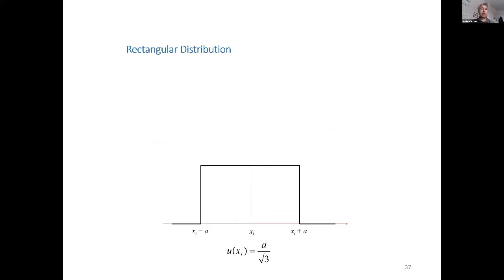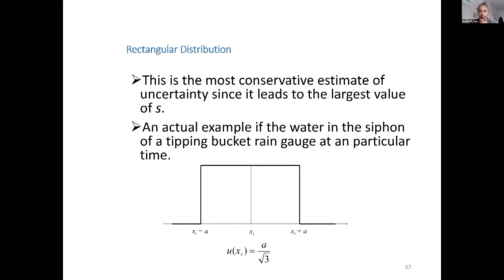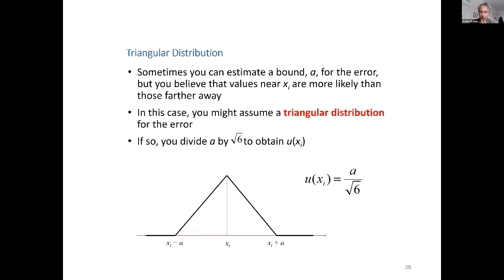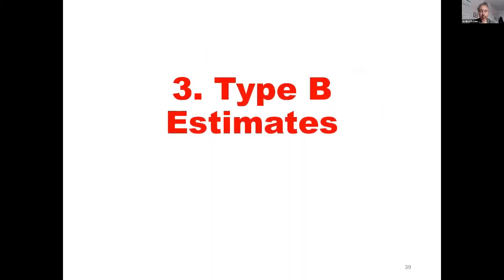Rectangular distribution is very much used in temperature when you know that you have, for example, a temperature stability that is equally given within a range of plus or minus 0.01 degrees, as the stability of your liquid bath during the calibration. It's rectangular. We used to keep it as rectangular. There are many other possibilities that went down. Well, you have pros and cons, but you read that square root of 3 is the way to calculate the uncertainty. And then you have the triangular one. I don't go into this, but I leave it for your records.